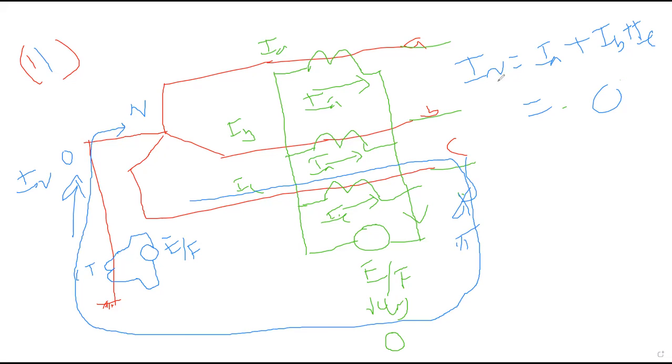And obviously, whenever a fault is involved, the balanced relationship between these phase currents is lost, and the current is not 0, right? So whenever you have the neutral current, your earth fault relay will also have current which is greater than 0, right? Yes, sir. So the relay will operate, isn't it? So this is how the earth fault relay can be placed.